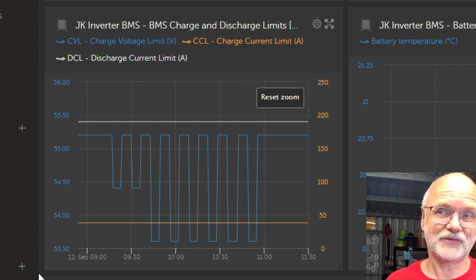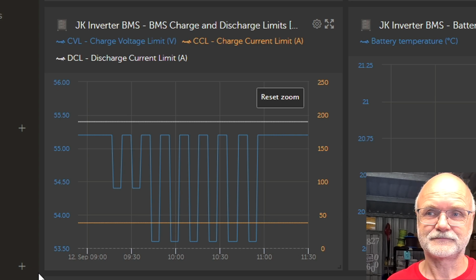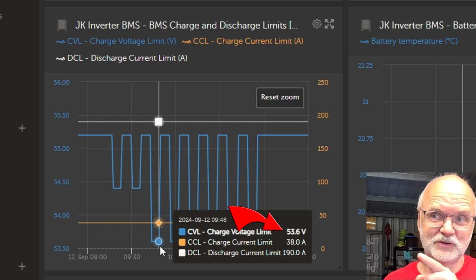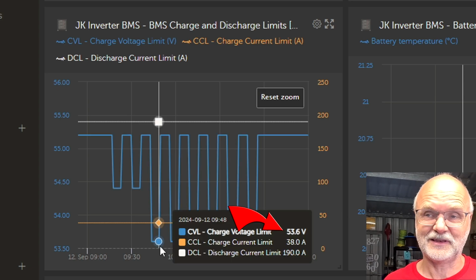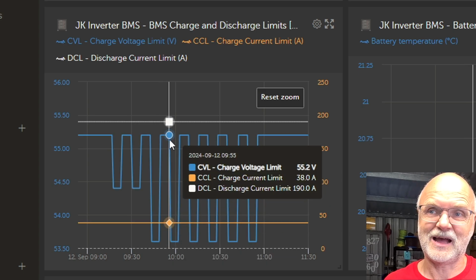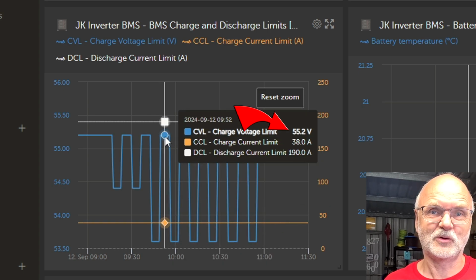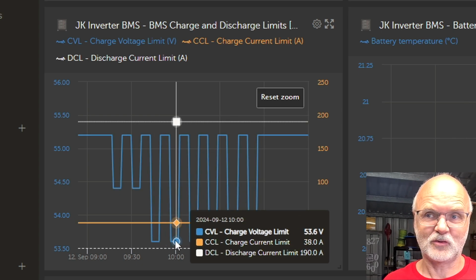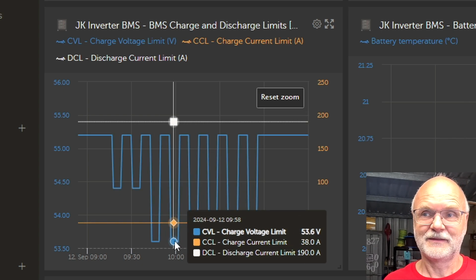The graph shows how these timers are triggering and changing the CVL, the charge voltage limit, in the Victron system, precisely every 6 minutes. Requested charge voltage 53.6 precisely, and then we jump back up and request 55.2. After 6 minutes, we go back into float mode because the timer has run out.